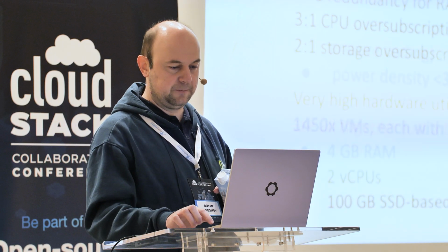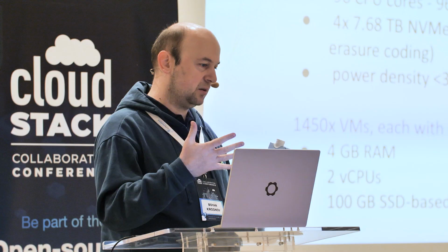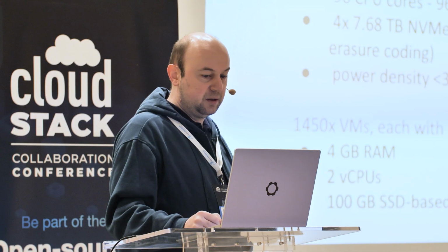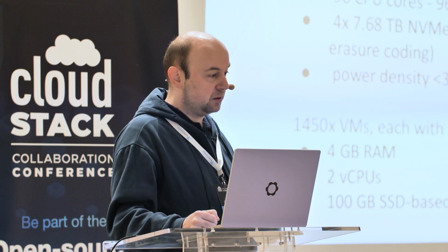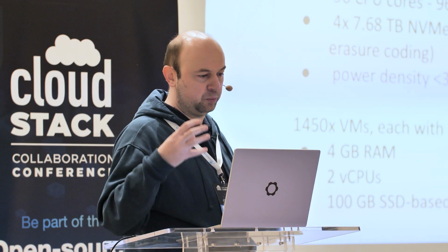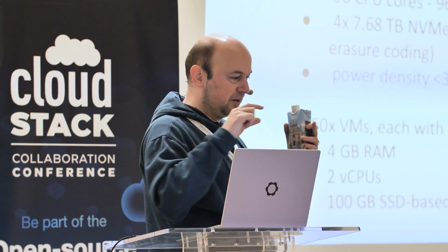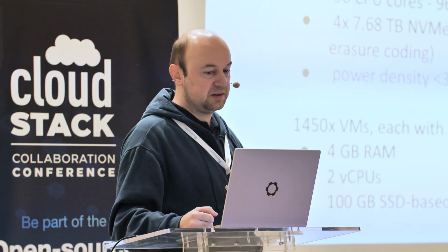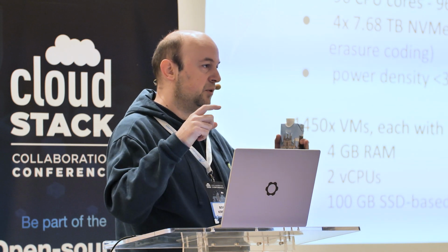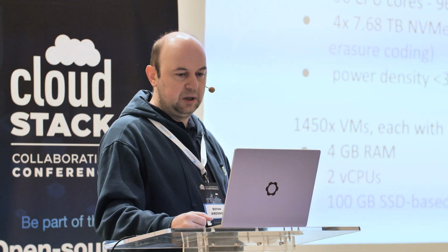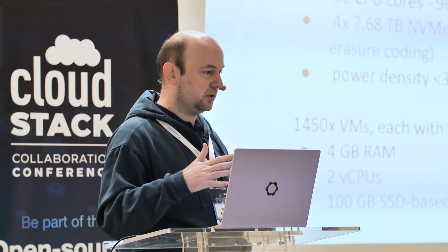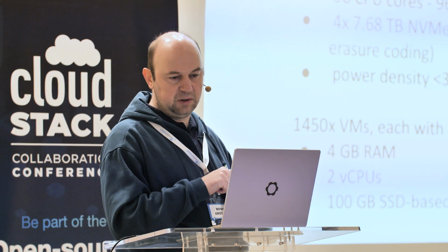This is often, in designing deployments, designing data centers, underestimated. Say you doubled the power density, the additional power you need to push that amount of air through a single rack unit is significant. It could be like 100 watts just to push the air you need to cool 500 watts in a single rack unit. So the lower density also helps with the overall efficiency of the power demands.